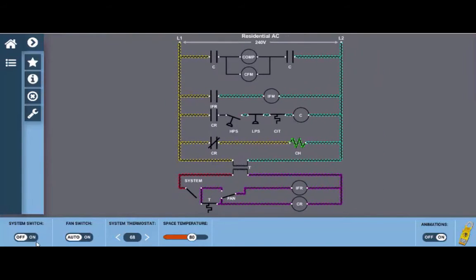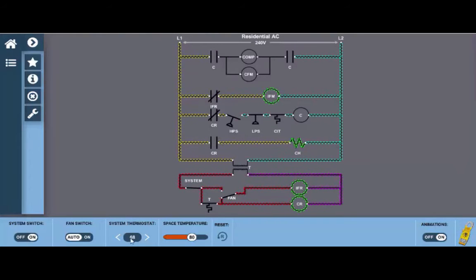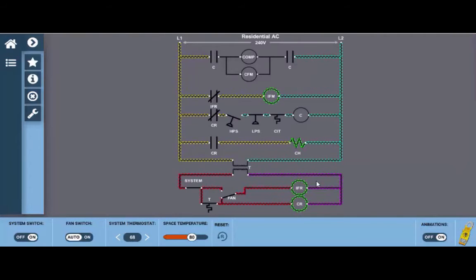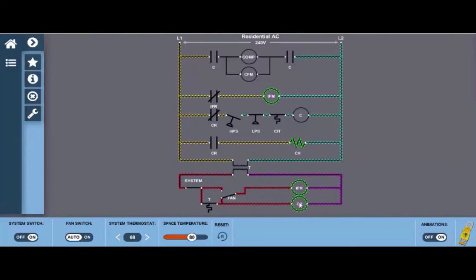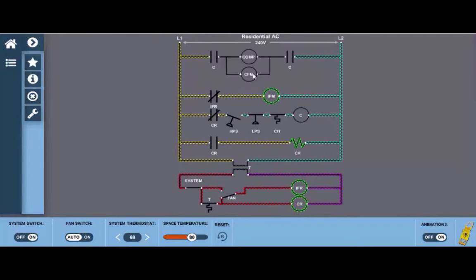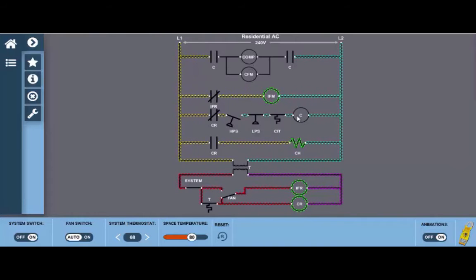I'm going to turn the system back on. I'm going to turn the thermostat set point below 80 which it's already at 68 degrees and if we look here we can see that although the relay coils are energized, the indoor fan motor is running, we have no compressor or condenser fan operation and this is because the contactor coil is not receiving power.